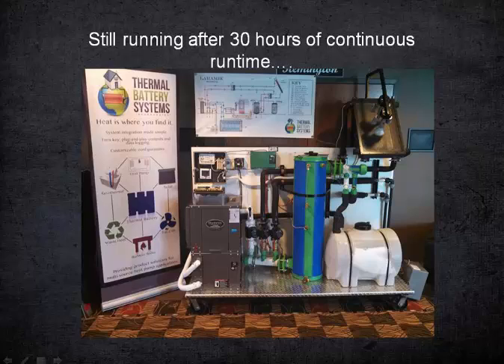And indeed, you can see the ice buildup on the lines leaving the source, the loop side of the heat pump there, and all over the outside of that tank. It had run for 30 hours continuously at this point. The entering water temperature to the heat pump was in the teens, but it was still operating. It had not locked out on low pressure yet, and we were starving it of energy. We weren't even really leaving the solar on much at all. And yeah, just a really neat little demo.